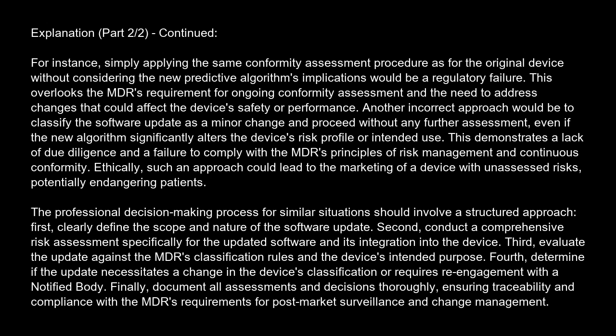First, clearly define the scope and nature of the software update. Second, conduct a comprehensive risk assessment specifically for the updated software and its integration into the device. Third, evaluate the update against the MDR's classification rules and the device's intended purpose. Fourth, determine if the update necessitates a change in the device's classification or requires re-engagement with a notified body.